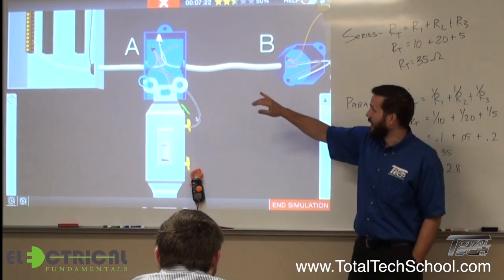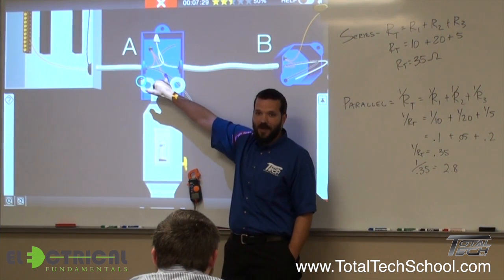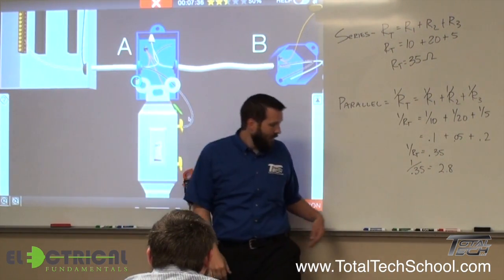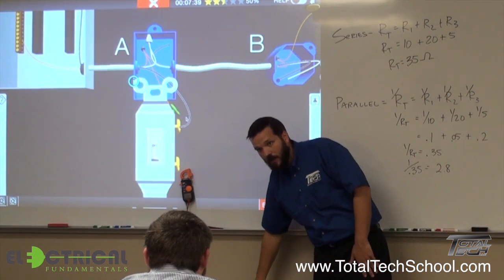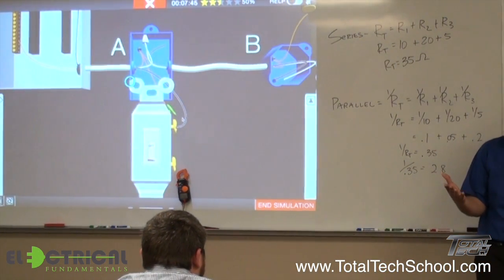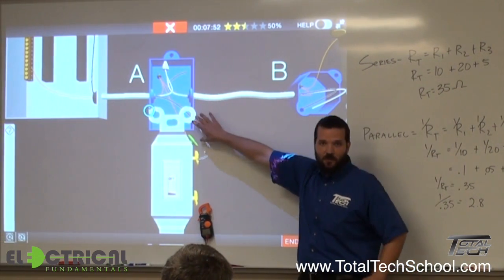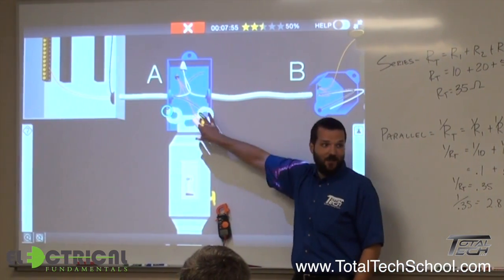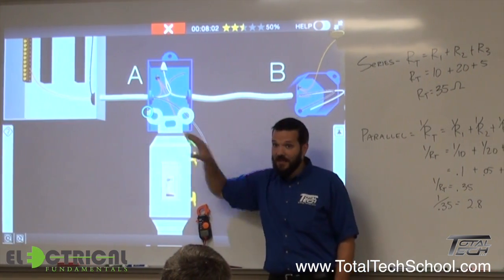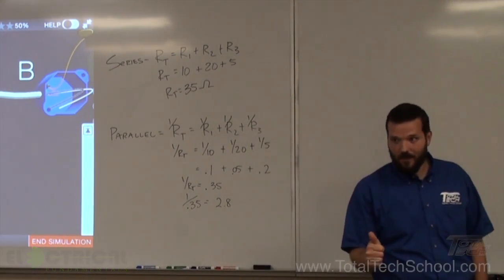So it's very important. Now, would it work if we tied this in? Is the potential difference between this equipment ground and this ungrounded conductor 120 volts in this case? Yeah, absolutely. We take our meter and we go to our grounding post on our plug to our hot, or to our ungrounded conductor. The potential difference, because ground is 0 and our hot is pushing at 120, is 120 volts. So yeah, that device would work. So in that particular case, functionality, it works, but it's not done correctly, and there's a safety element there that hasn't been taken into consideration. So functionality is not our number one goal.